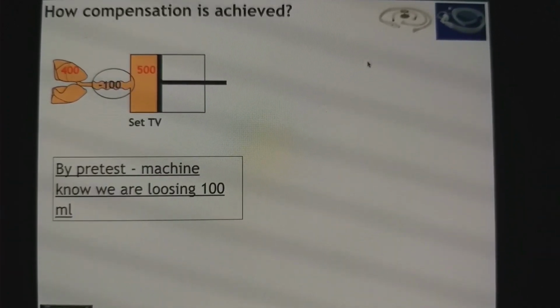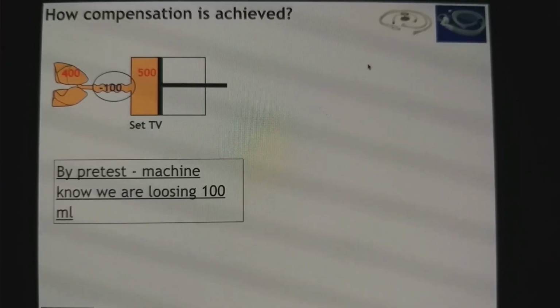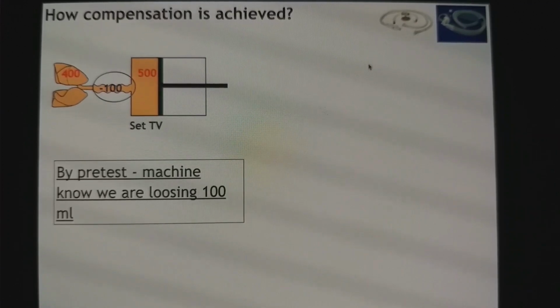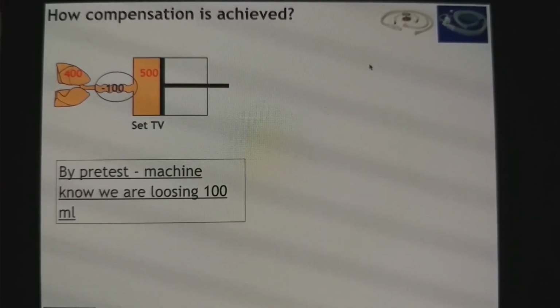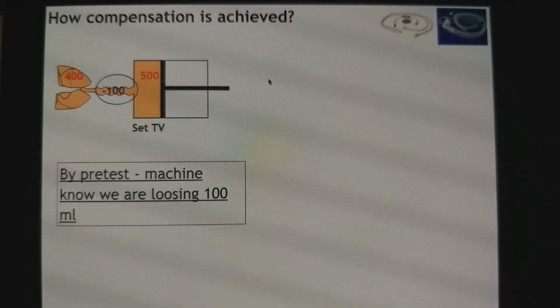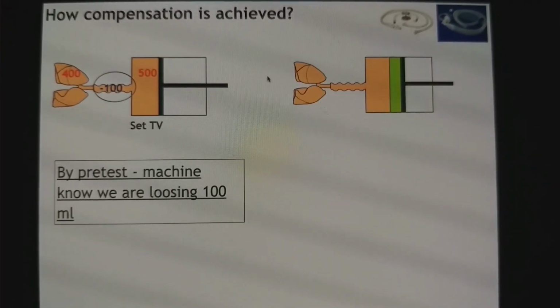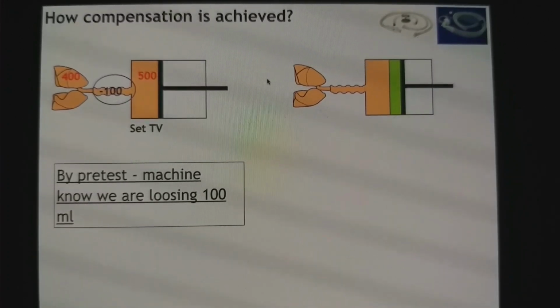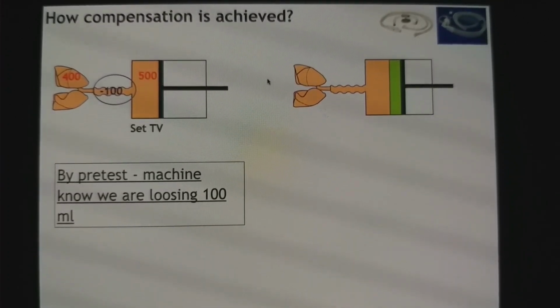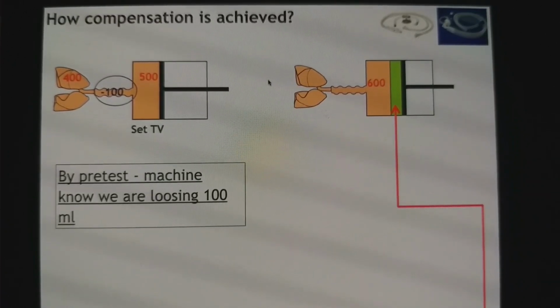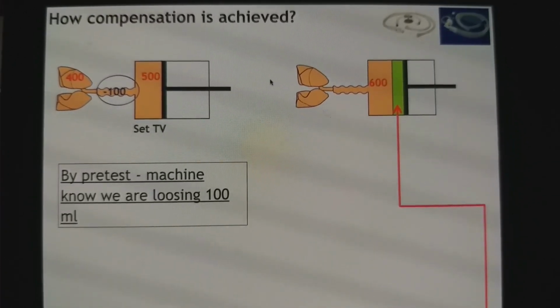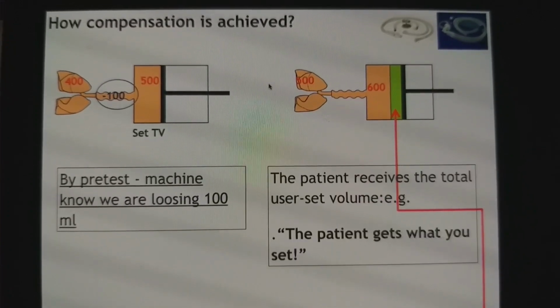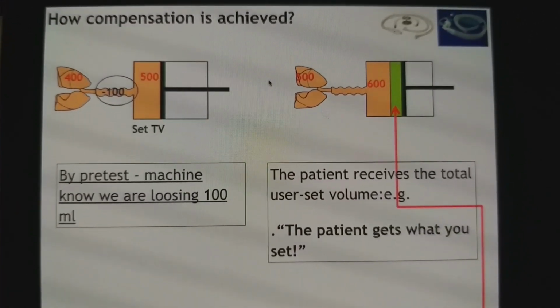Now, how is compensation achieved? Suppose you have set a 500 ml tidal volume, and 100 ml of gases are lost on the way, so your end result would be 400. The machine, by pre-testing, knows that we are losing 100 ml, so it will deliver 100 ml extra. So it will deliver 600 ml, which will compensate for the wasted ventilation, and the patient will get 500 ml. But this is provided you have done the leak and compliance test.